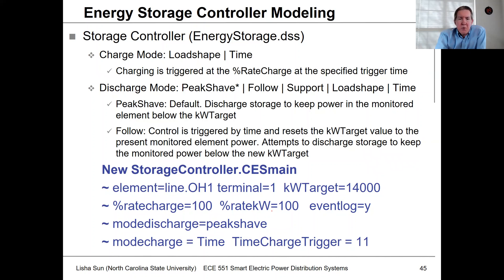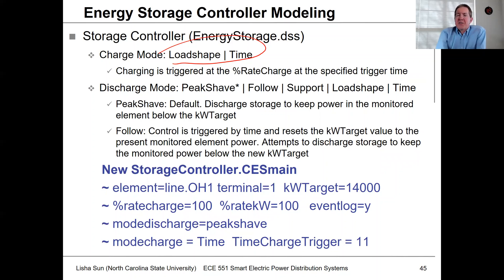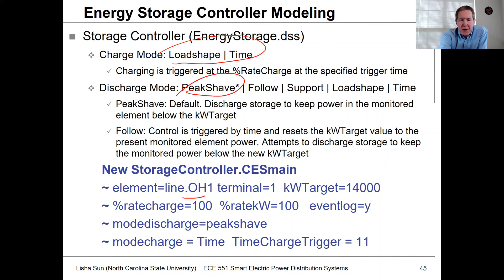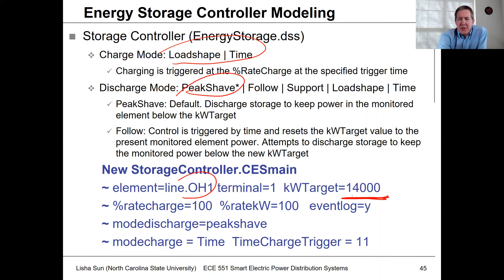We also need to set up a controller. In this case, we're charging based on a load shape — basically charging at the peak. For discharge, we're doing peak shaving at the top of the feeder. The control point is at the overhead line at the top of the feeder, and we're trying to keep the kilowatts below a set value. There are also ramp rate limit settings available.